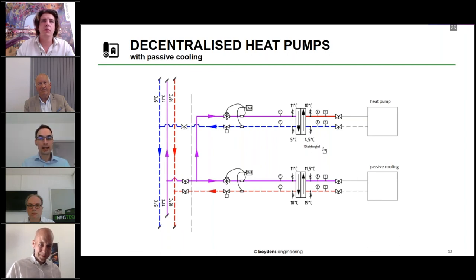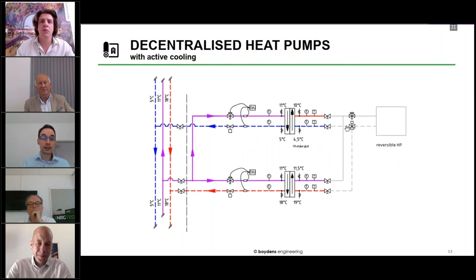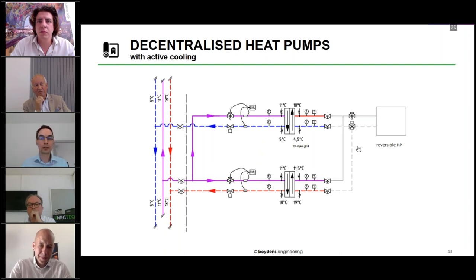We also have, in that case of heat pumps, 10% of ethylene glycol, so that if there is a freezing danger, there is no freezing in the heat exchanger of the heat pump. Now, the second possibility that is also applied on the site is heat pumps with active cooling. What happens here is that there is a switchover valve on the secondary side of the heat pump. Depending on the mode that the heat pump is in, heating or cooling, the water will then be distributed to the right heat exchanger so that it can be rejected back into the loop.